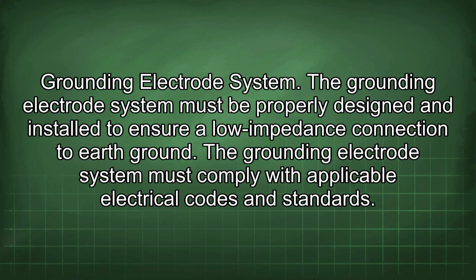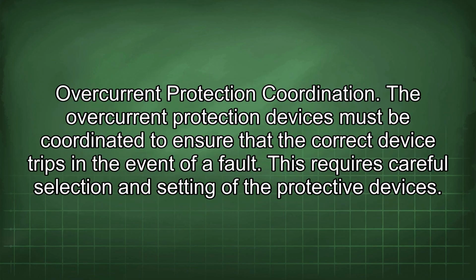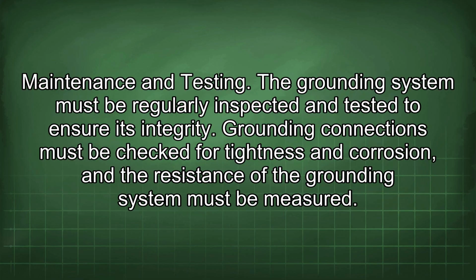The grounding electrode system must comply with applicable electrical codes and standards. Overcurrent protection coordination. The overcurrent protection devices must be coordinated to ensure that the correct device trips in the event of a fault. This requires careful selection and setting of the protective devices. Maintenance and testing. The grounding system must be regularly inspected and tested to ensure its integrity. Grounding connections must be checked for tightness and corrosion, and the resistance of the grounding system must be measured.